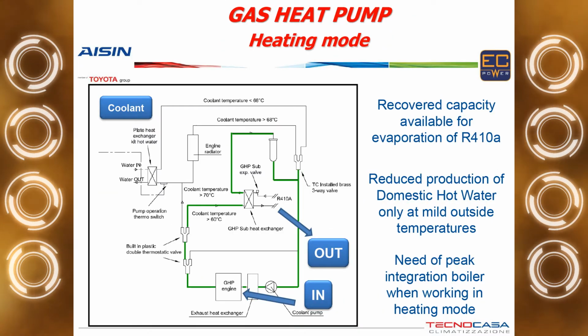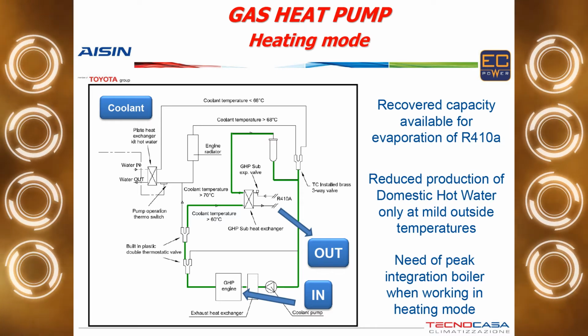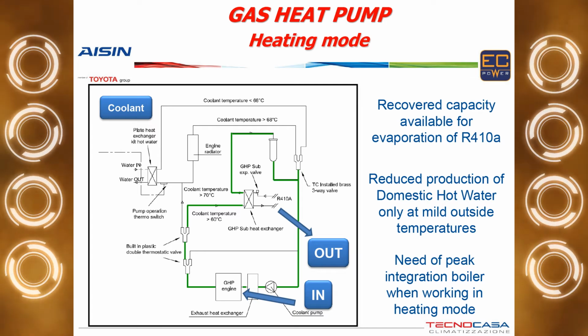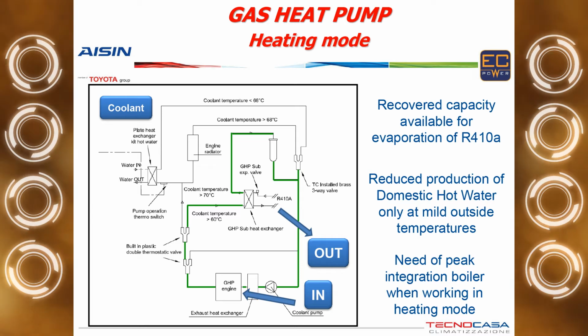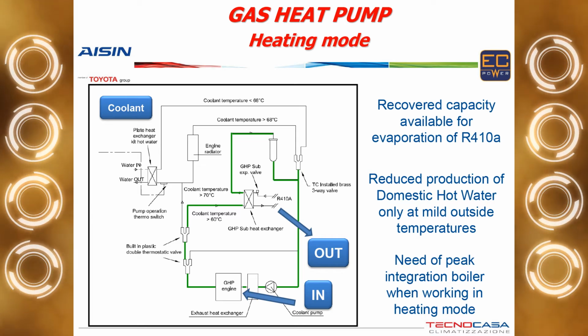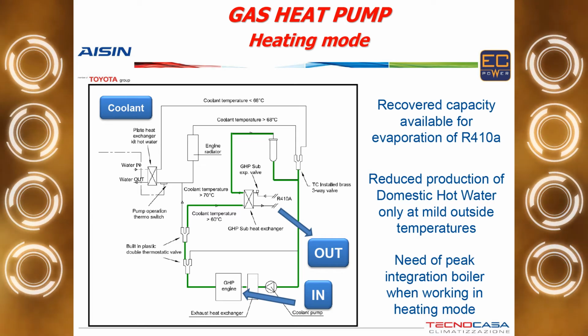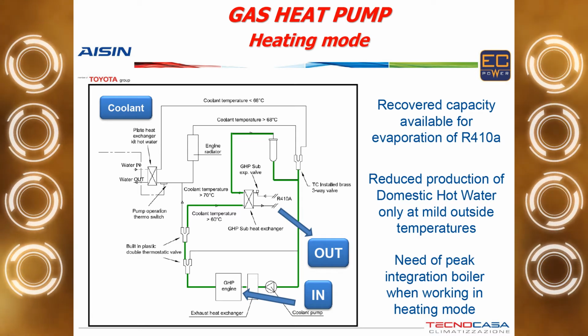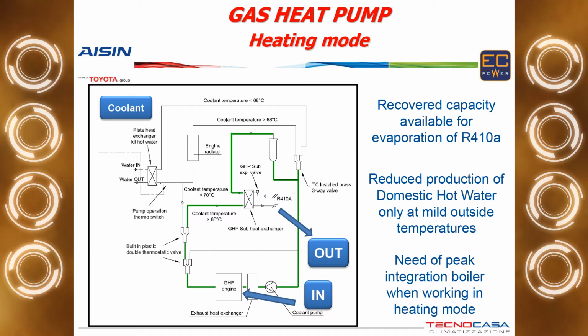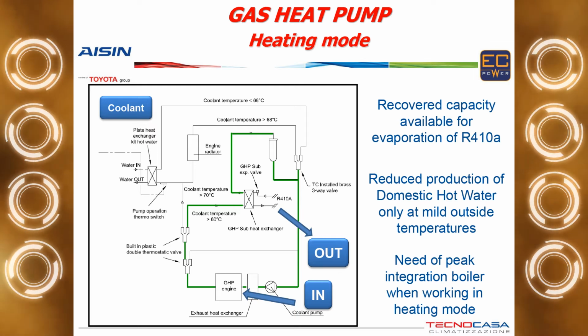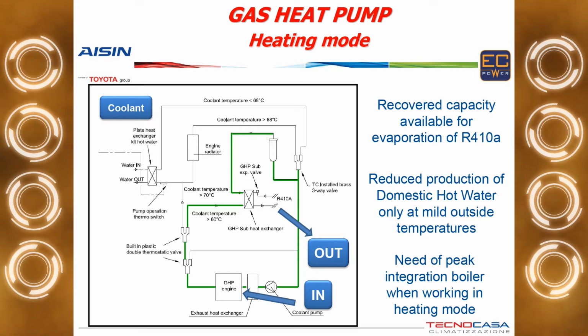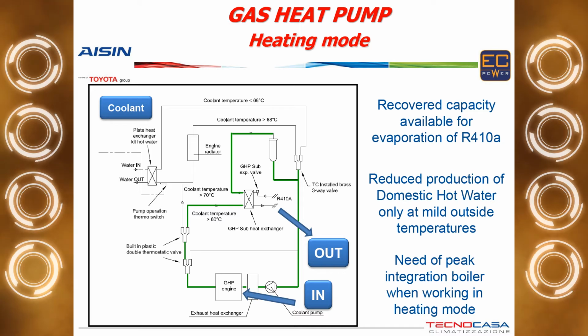Things change when we start working in heating mode. This is because, of course, we reverse the cycle, but we do not use only the air to evaporate the refrigerant gas. We also use the engine coolant. So, again, we take the mechanical energy from the engine to drive the compressors. The gas goes into the indoor unit where the condensation happens, and so it releases the heat to the indoor of the building. Then it goes back to the outdoor unit, and the most important thing is that on the way back there is no pressure drop, so this expansion valve is always open during the heating mode.